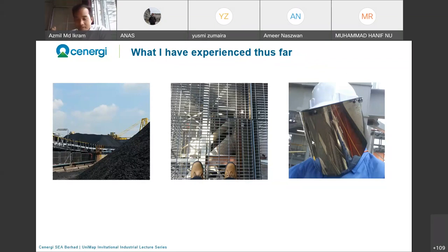You peek at a hole, and you either look down or look up, and then you see the flame, how big it is, the shape of the flame, where it goes. Then you look at the walls for any residue, what we call slag, molten coal that is stuck on the wall. Then we can indicate, this is our observation. You have to do such and such to operate your power plant. Those are the advisories that we give.